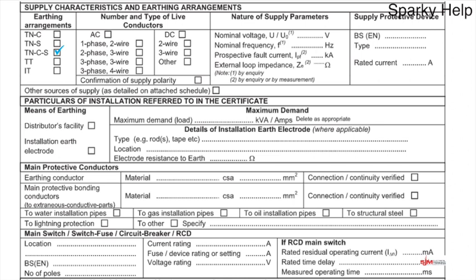We can basically look at an installation. So the vast majority of installations you would use would be AC, and hopefully we can see that up there. We've got 1 phase 2 wire, that would be a single phase installation. And if we were doing a normal 3 phase installation with a neutral, we would be ticking 3 phase 4 wire. 3 phase 3 wire would be without a neutral. 2 phase 3 wire, you've got 2 phases and a neutral, so some properties may well have 2 phases coming in. Maybe the incoming single phase wouldn't have been big enough because they're miles down the end of a track or something like that, but if you do have it, we've got the availability. So we're going to base ours on AC. We had a single phase installation, so it'll be 1 phase 2 wire.